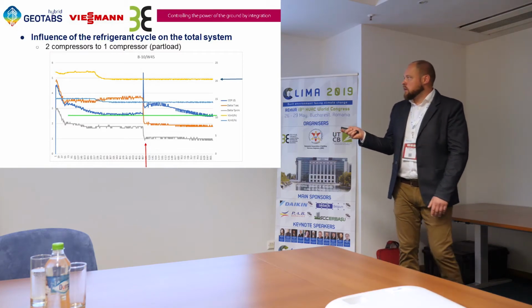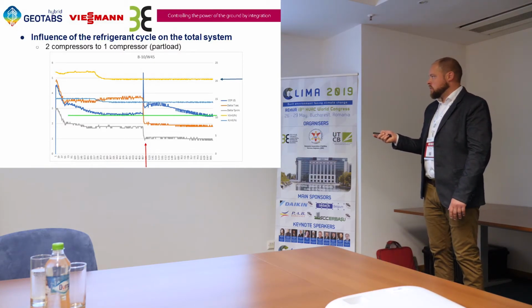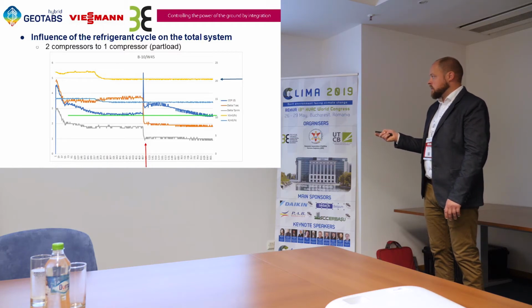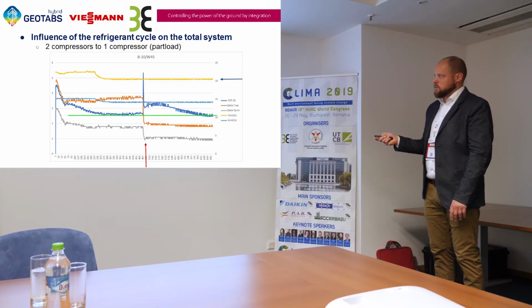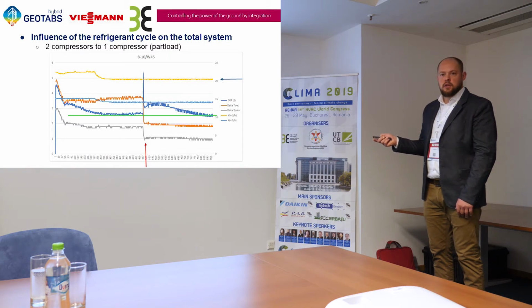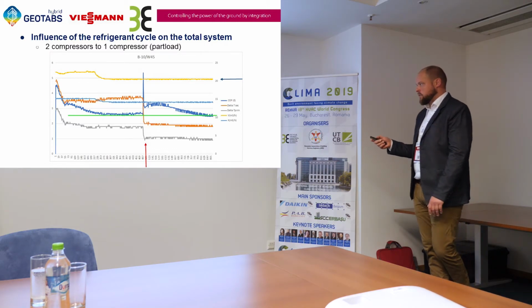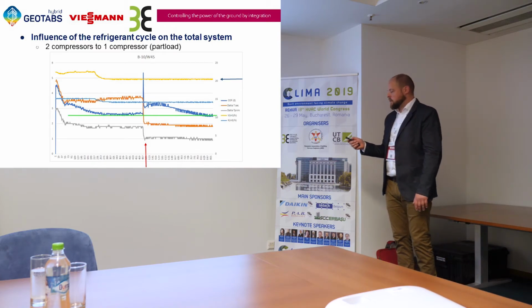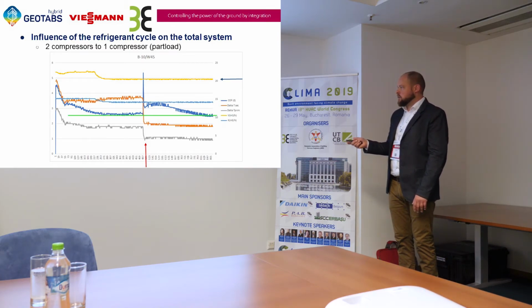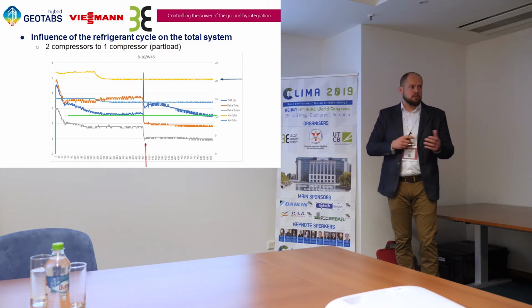Here you can see a stable running machine. The flow through the condenser is shown here. It's a stable flow, and you can see at this point we switch from 2 compressors to 1 compressor. It has a small peak in COP, but that's just because of the power change. Then you can see the COP rises a bit, but it will stabilize in time at the same point as it was before. See here. So it's not that big of a difference if you run on 1 or 2 compressors.